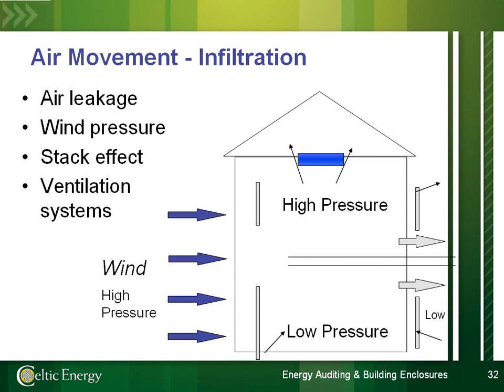So this next slide describes, again, more of this energy transfer caused by air movement. And this slide shows that the mechanical system can also have a significant effect on this, because when we set up our ventilation systems, we often try to do a balancing at the startup of the building, a balance between outdoor air for good air quality and then exhaust air from the building to maintain just a slight pressurization so that air can be conditioned, humidity can be controlled, and you won't get intrusion of unconditioned air from outside. If over time that fan balance is upset, it can create real difficulties and fundamentally change those relationships.